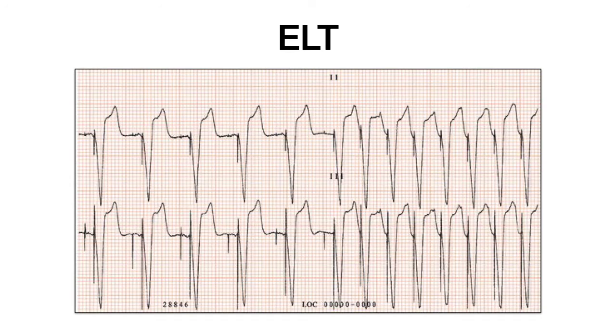The endless loop tachycardia, or pacemaker-mediated tachycardia, or circus movement tachycardia, is not a portion of the timing cycles of the pacemaker. But to understand why it happens, you should be familiar with the timing cycles of the dual chamber systems. It is a re-entry arrhythmia in which the pacemaker acts as the anterograde limb of the tachycardia and the AV node acts as the retrograde limb.